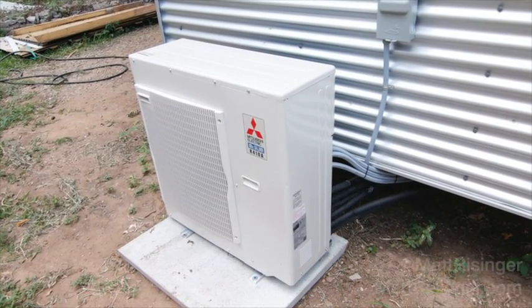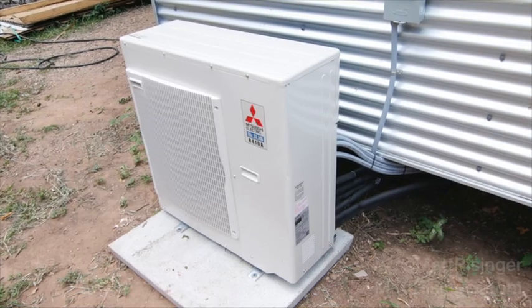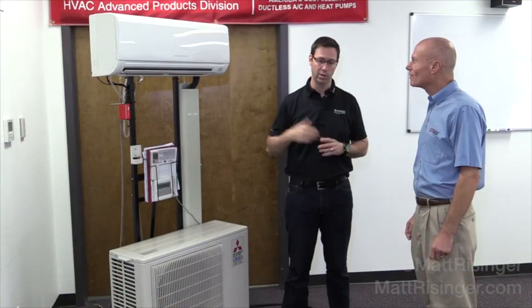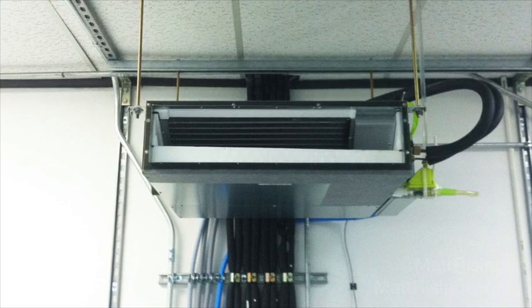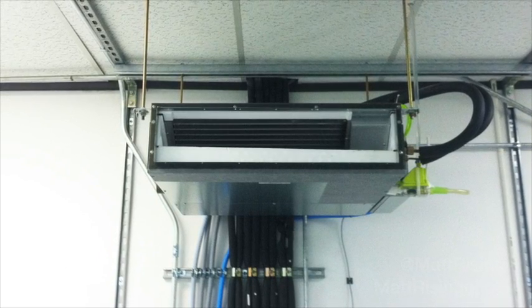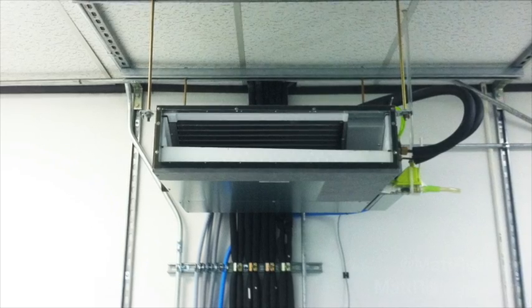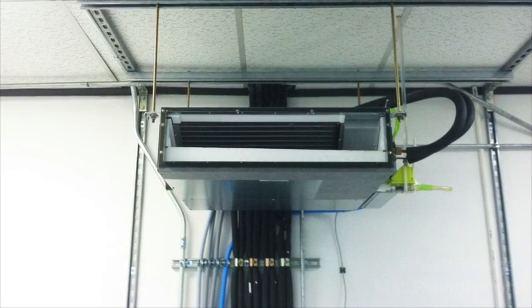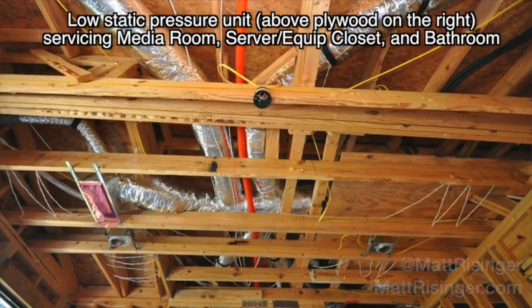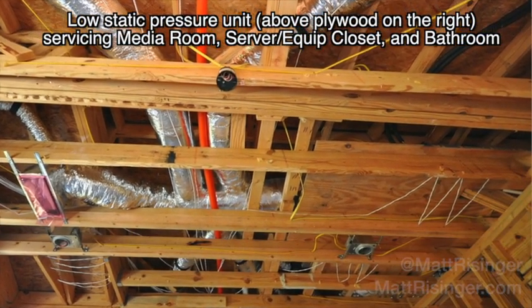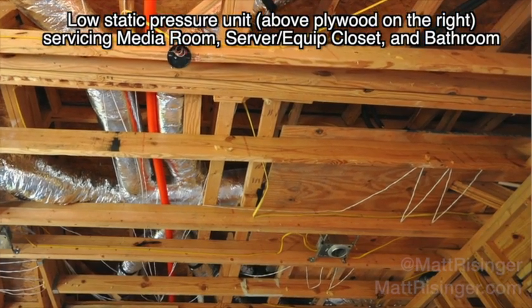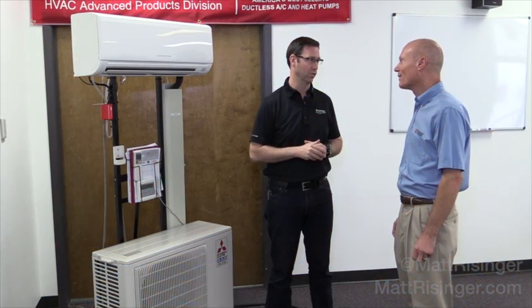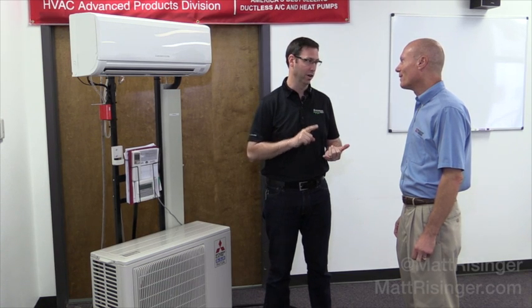They also have a bunch of different options besides the mini-split head. They make a radiator style unit you'd see at the floor, and some low static pressure blowing units we often call the pizza box, about the size of a couple pizza boxes stacked up, with a little pair of plenums attached. You might service two rooms, like a master bedroom, master bath, and master closet with one of those, zoning your house very efficiently. I've got a house under construction now with 8 zones, all Mitsubishi, tied to 3 compressors outside. It's amazing what you can do with these, running efficiently and very quiet, giving you great options.